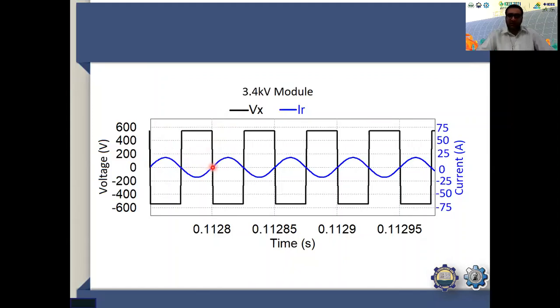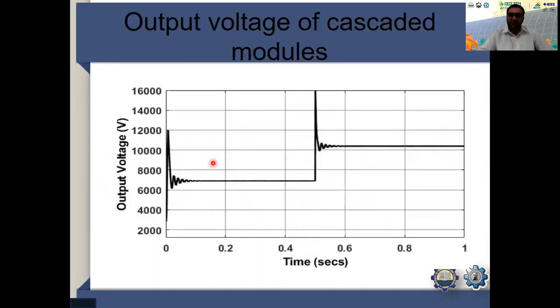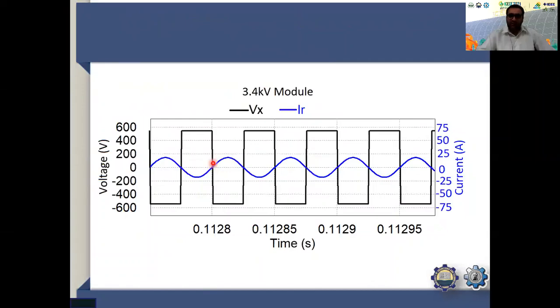This topology was specially preferred due to this particular feature, because this is a power-intensive application. The current at the primary side of the transformer will be very high, and non-zero switching, or you can say hard switching, could not be tolerated. The power switching losses would have been very much increased. Therefore, we remain with this topology.